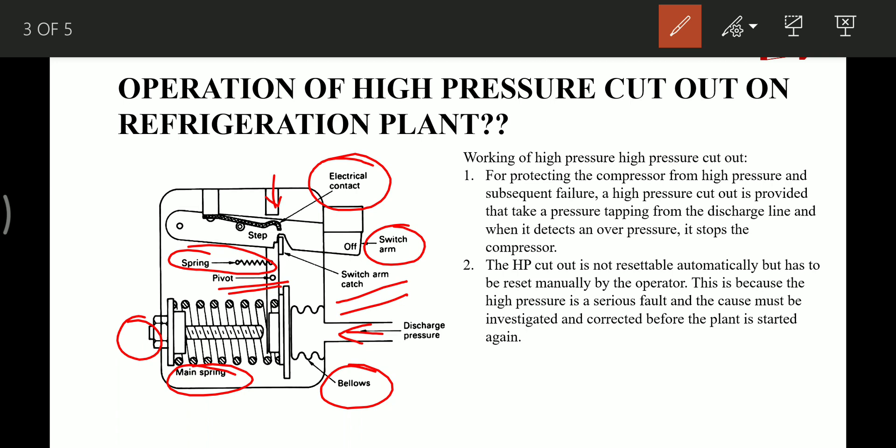For protecting the compressor from high pressure and subsequent failure, a high pressure cutout is provided that takes a pressure tapping from the discharge line. When it detects an overpressure, it stops the compressor. These high pressure cutouts are not resettable automatically but have to be reset manually by the operator. This is because high pressure is a serious fault and the cause must be investigated and corrected before the plant is started again.